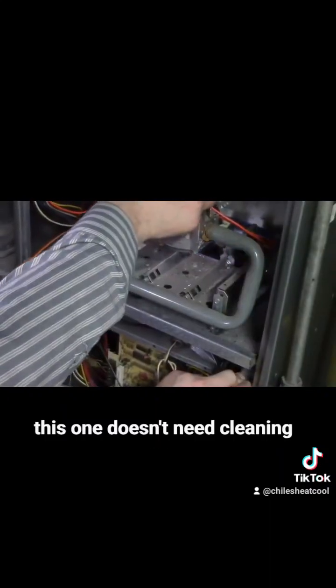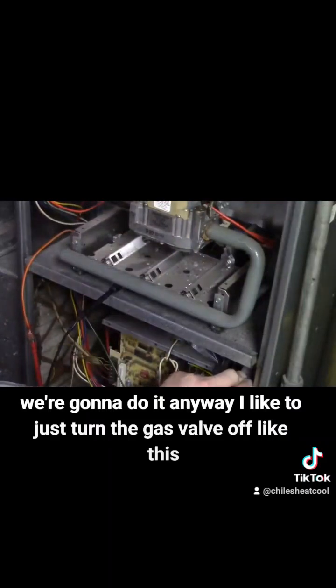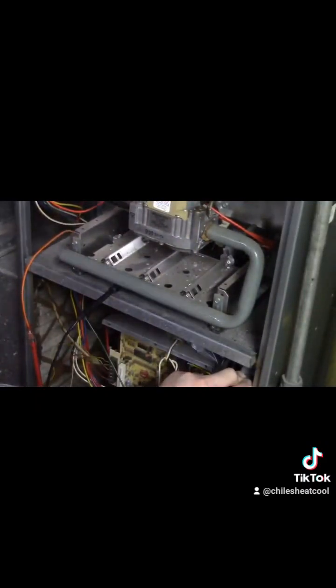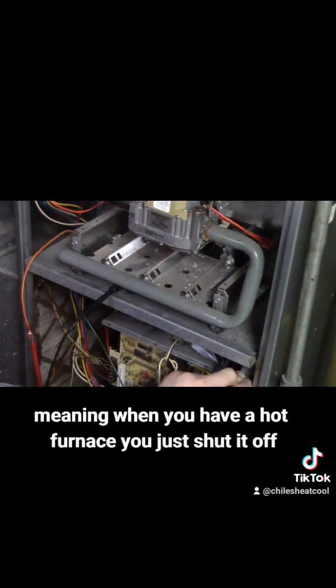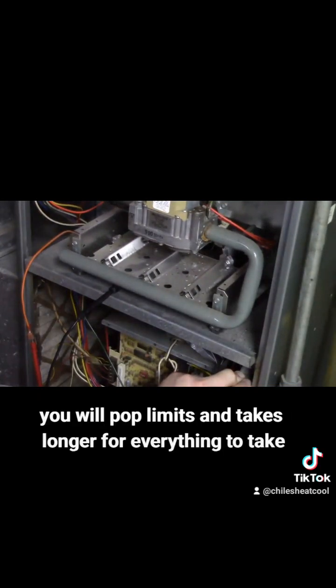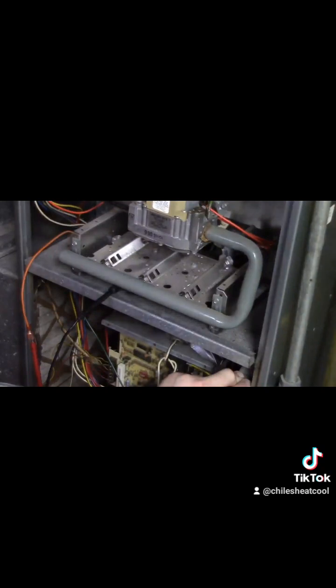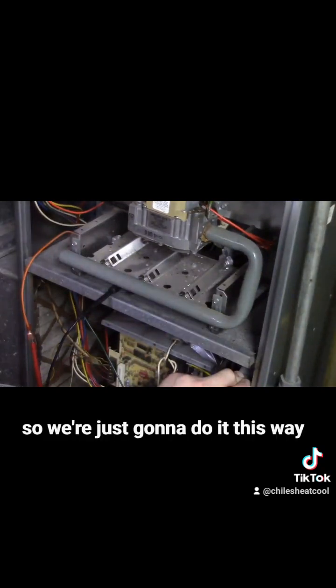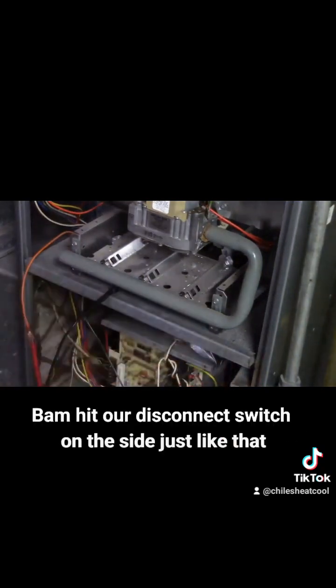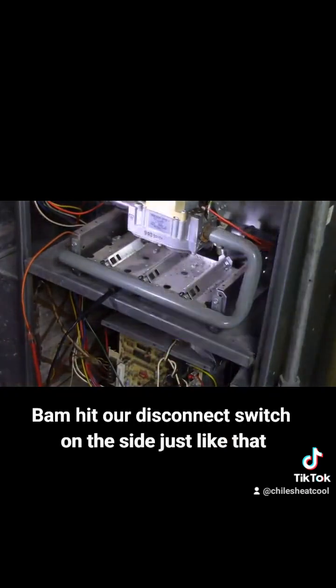This one doesn't need cleaning. We're going to do it anyway. I like to just turn the gas valve off like this. Meaning when you have a hot furnace, you just shut it off. The heat exchanger stays hot. You will pop limits. It takes longer for everything to do what it's supposed to do. So we're just going to do it this way. Bam. Hit our disconnect switch on the side, just like that.